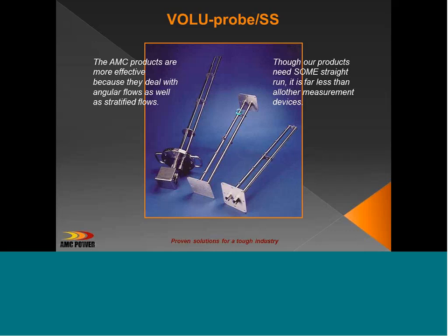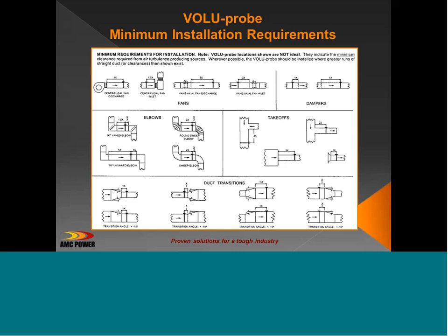But when we get into a burner, regardless of the technology, whether it's an air monitor technology, whether you're using an orifice plate, or whether you're using a thermal anemometer, there are always straight runs associated. You cannot put measurement devices just anywhere, and these are the air monitor straight run requirements for a VOLU-probe.